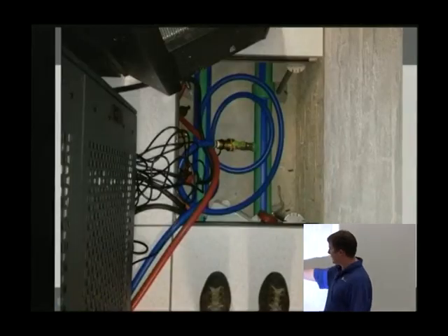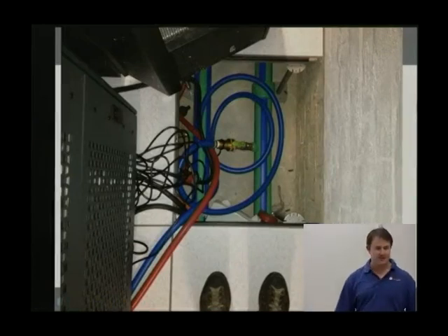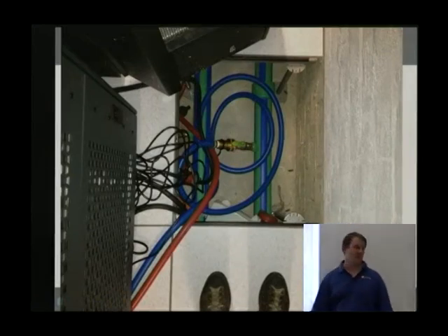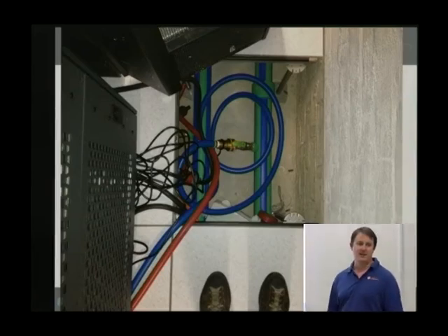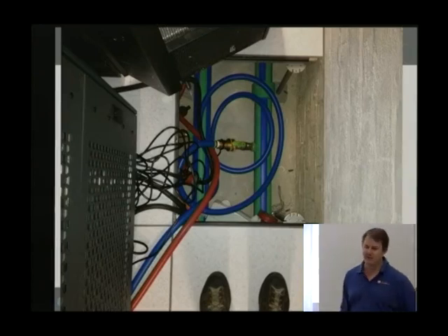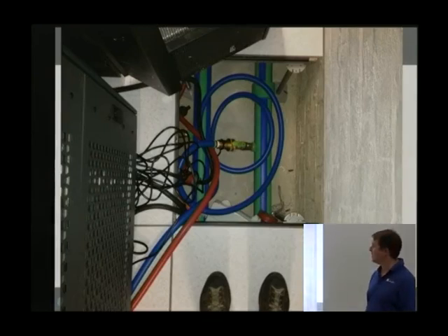Of course, then you have these pipes of water running around the bottom of your machine room, which makes a lot of people nervous. Water, computers. We've never had a problem. Been doing this for 5 or 6 years, and we've never had a water leak. The only time we get water in there is when we get a blockage and I'm jamming a screwdriver in to try and free it, and then water pours out all over the floor when it gets released. That's about the only time we get water, but everything handles a bit of water these days, so it's not really a problem.